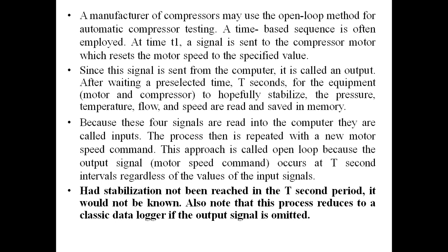The signal sent from the computer is called an output. Because these four signals are read into the computer, they are called inputs. The process is then repeated with a new motor speed command. This approach is called open loop because the output signal occurs at T-second intervals regardless of the values of the input signals. Had stabilization not been reached in the T-second period, it would not be known. Also note that this process reduces to a classic data logger if the output signal is omitted.